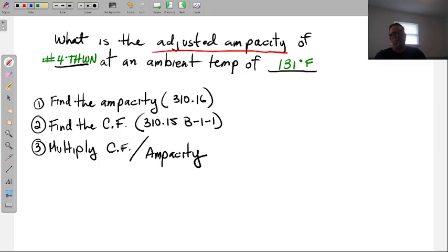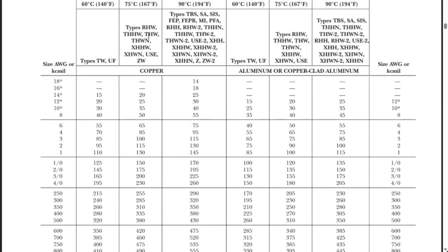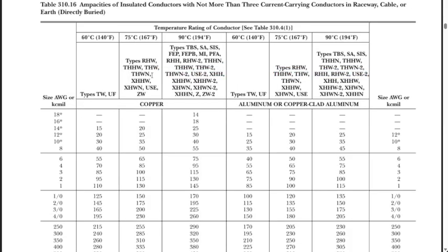All right, so hopefully the steps were easy to follow. Now, this one, we're not treating like any specific column, 60 or 75. We ignore all that, although there's no amperage to really take us into any of them. We're looking for the insulation type, which we find in the 75-degree column. Remember out of step 1, two things we take note of: the amperage from the wire, number 4, 85.